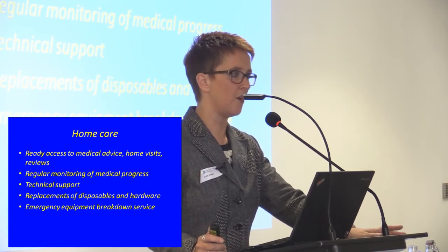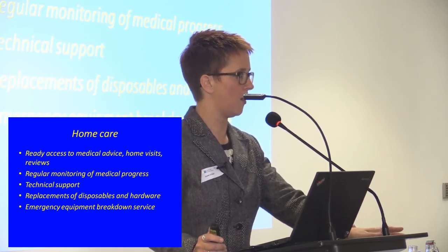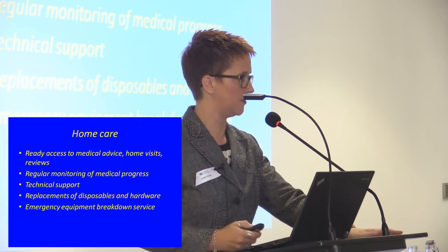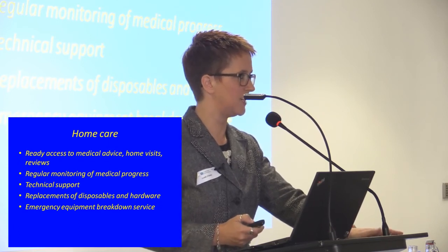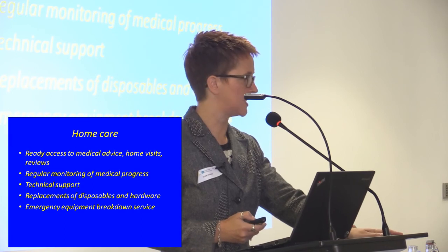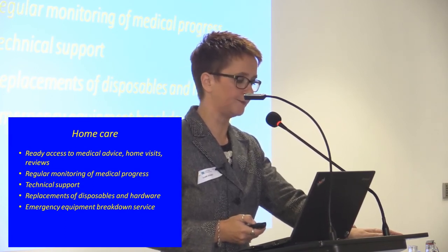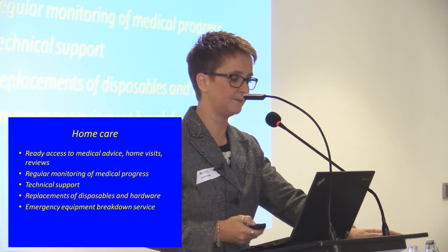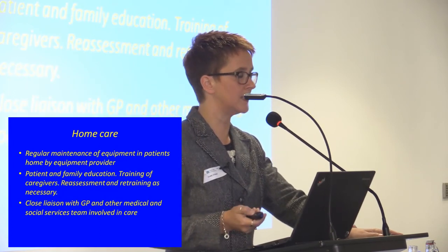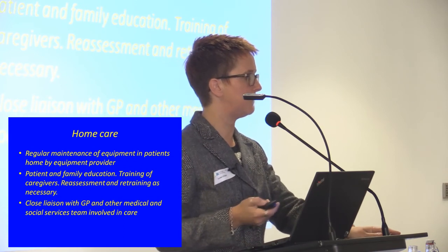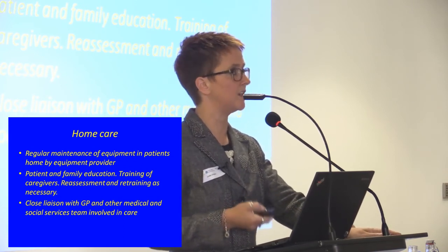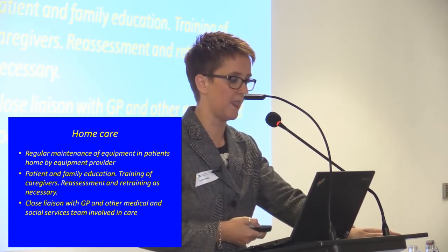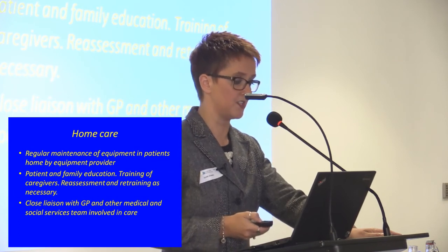Replacements of disposables and hardware. A lot of the masks are hard wearing. It's usually the headgear that goes first. So if you see it getting really sort of broken down and not sticking, etc. on the patient, you can contact myself or Respiratory or the team that's dealing with the machine. Regular maintenance, regular family and patient education, and regular retraining and education is very, very good and necessary for this to work.